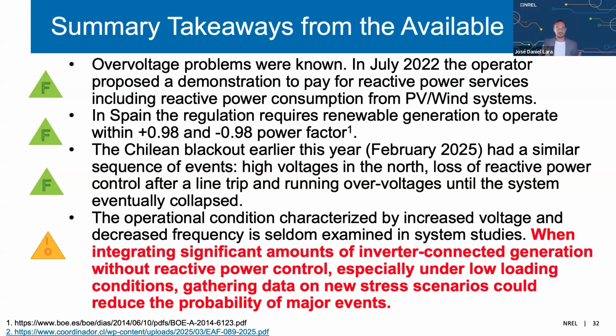And I think this is important because a lot of the conversation has been about what the primary energy source behind these generators is. What the data shows us is that if you had put any source of power, but forced those generators to operate within such a narrow power factor window, the physics of power system transmission, the lack of loading of the transmission lines, and the excess reactive power would have caused the same type of event. The other interesting thing is that early this year, we had a blackout in February 2025 that had a similar sequence of events.